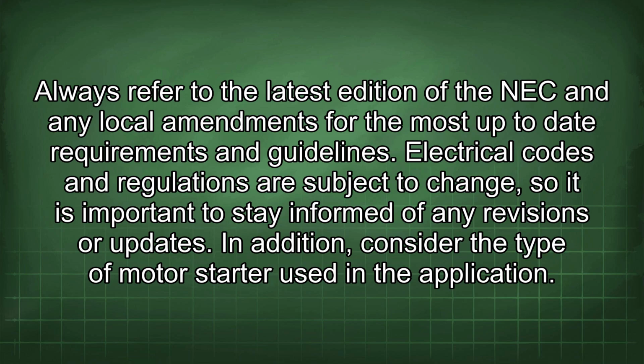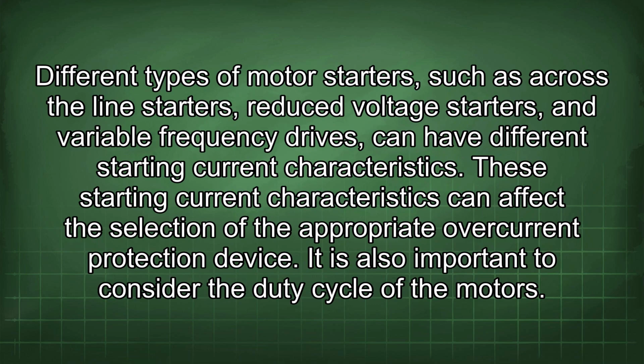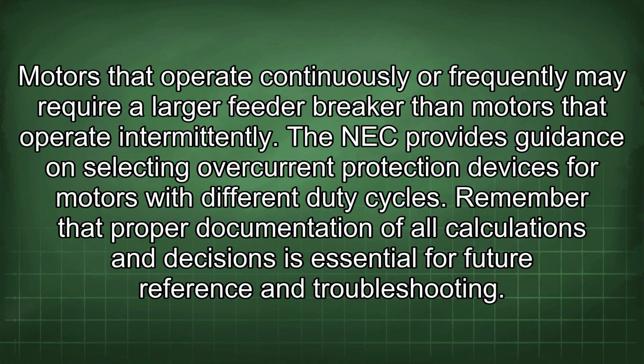In addition, consider the type of motor starter used in the application. Different types of motor starters, such as across-the-line starters, reduced voltage starters, and variable frequency drives, can have different starting current characteristics. These starting current characteristics can affect the selection of the appropriate overcurrent protection device. It is also important to consider the duty cycle of the motors. Motors that operate continuously or frequently may require a larger feeder breaker than motors that operate intermittently. The NEC provides guidance on selecting overcurrent protection devices for motors with different duty cycles.